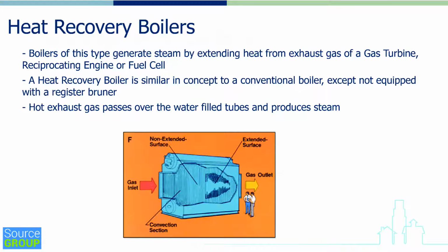Heat recovery boilers. Heat recovery boilers are covered here just so you get a sense of what device is used to recuperate the heat from the generation process. Boilers of this type can generate steam. Also, in some cases, they generate hot water, high temperature hot water in many cases, by extracting heat from the exhaust of a gas turbine or a reciprocating engine or even a fuel cell. The heat recovery boiler is similar in concept to a regular boiler, except that it's not equipped with a burner. Hot exhaust passes over water-filled tubes and it produces steam.